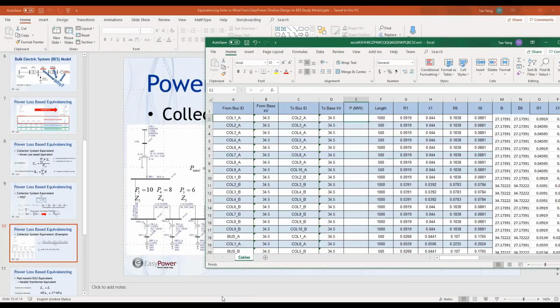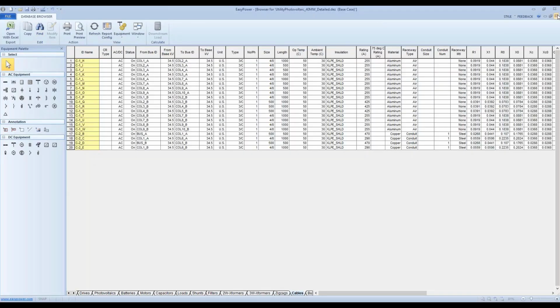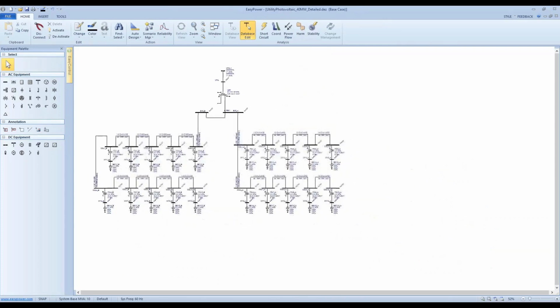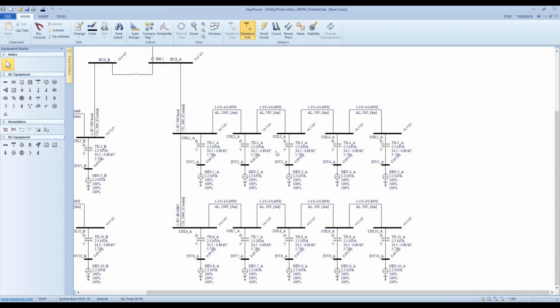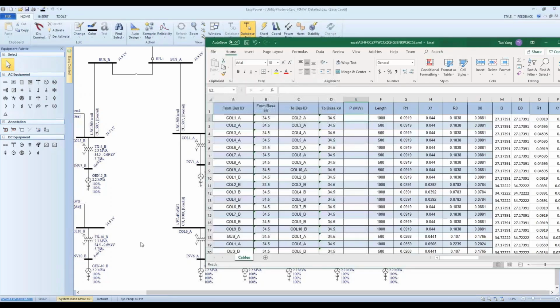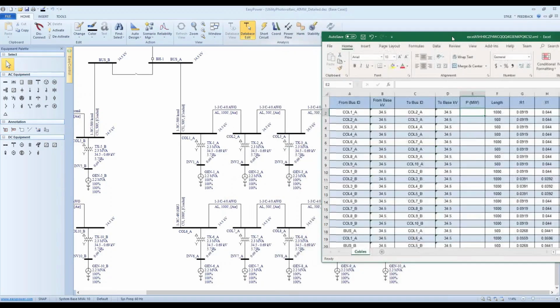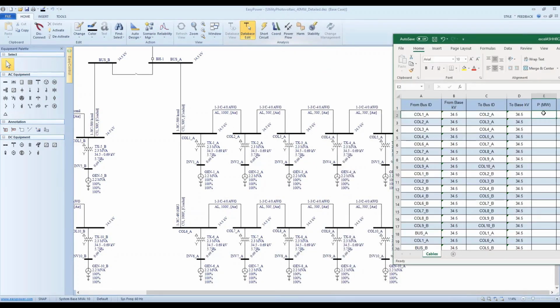And then let's go back to EasyPower one line to check how much active power flows through each circuit. So from collector 1A to collector 2A, from the design, you can say I have 8 megawatt because I have 4 inverters as my upstream inverters, right? I have 6 here, 4 here, 2 here. For my collector 6A to 7A, the same topology would apply: 6, 8, 6, 2, 4.